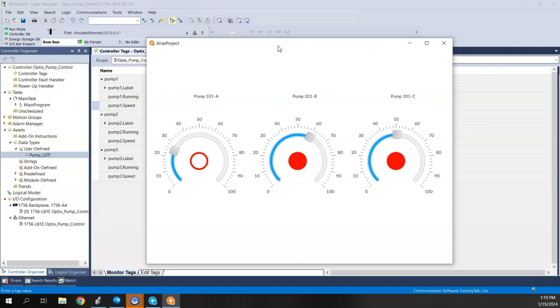We created UDTs, brought them into Optics, created a faceplate with an alias linking back to the UDT type, and quickly reused the object by assigning it to the right UDT for each pump. This is what's called resolving at design time — everything is configured during design, and that configuration is used at runtime. The other method is resolving at runtime, where an index is used to choose which set of pump data to bring into the faceplate — that will be covered in another video.